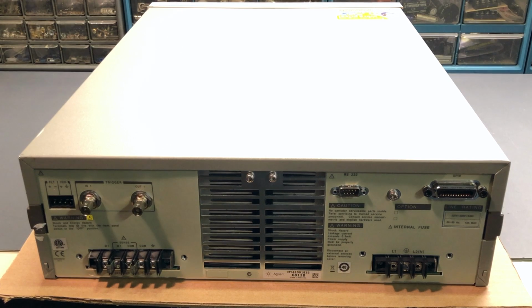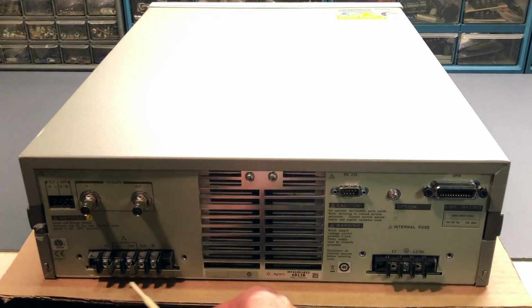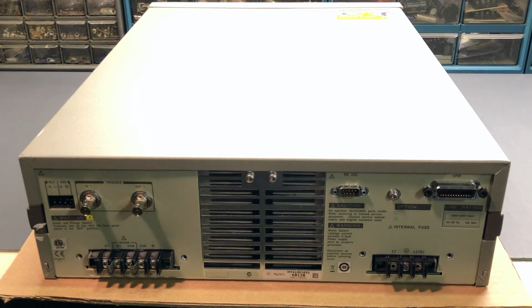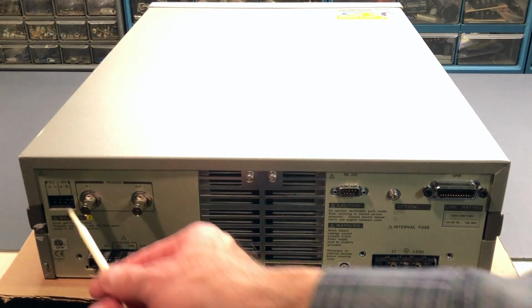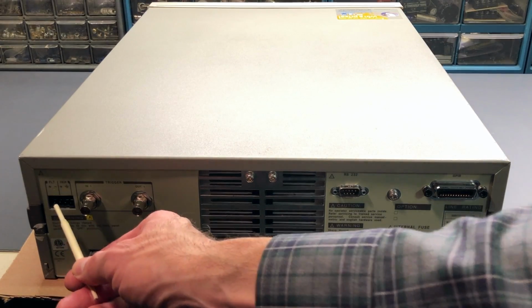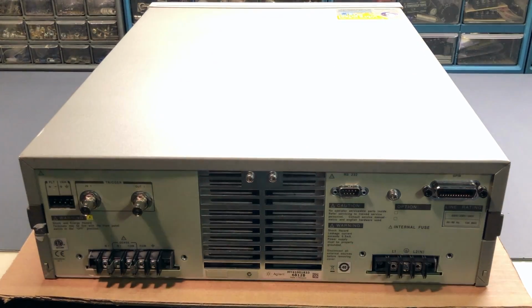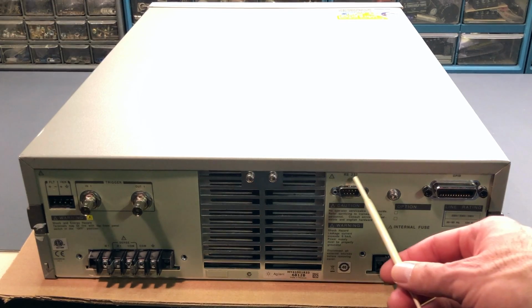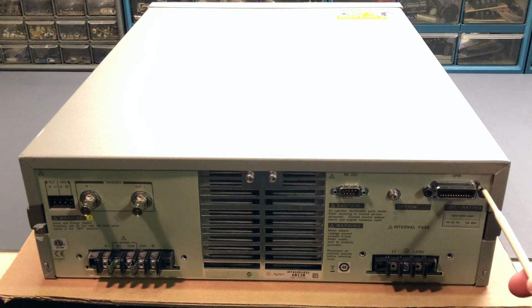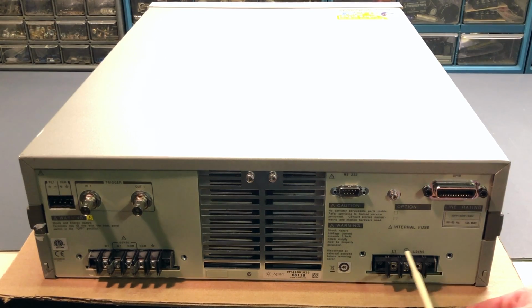Okay, taking a look at the back panel of the instrument, there are several things that I wanted to mention. So this terminal board right here is for the AC line input connection, and this terminal board over here is the output from this power source where you make the connection to the device that you want to power. In this corner over here is some auxiliary functions on this connector, and these two BNC connectors are for some triggering controls. Right here's an RS-232 connector for a computer interface, and right here's a GPIB connector for remote control of the instrument. Now you can see on this terminal board, two of the screws are missing, so I need to find replacement screws for that terminal board.